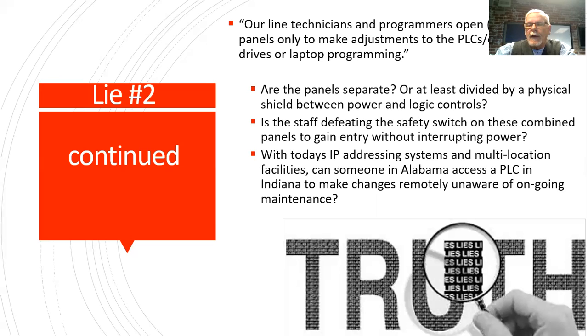Regardless, you're going to have a two-sided panel. The programmer's got the doors open. He's only working, or she's only working, on the PLC or the logic side of the panel. If there is not shielding between the power side and the PLC side, or if there's no separation, those folks are being exposed to whatever that voltage is. That's a problem. Something we need to be aware of. A lot of times with these dual cabinets, the disconnect is always going to be on the right-hand side, usually up in the upper right corner on the outside of the cabinet.